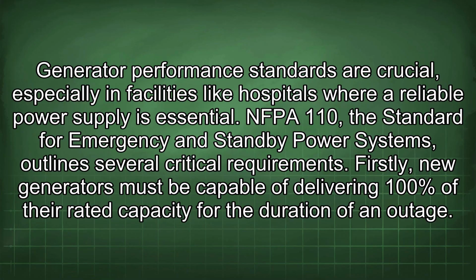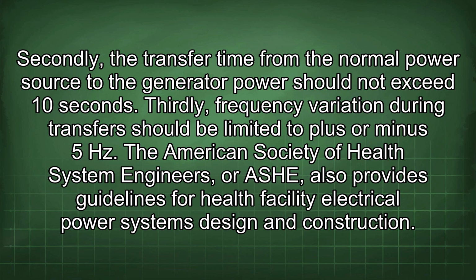Generator performance standards are crucial, especially in facilities like hospitals, where a reliable power supply is essential. NFPA 110, the standard for emergency and standby power systems, outlines several critical requirements. Firstly, new generators must be capable of delivering 100% of their rated capacity for the duration of an outage. Secondly, the transfer time from the normal power source to the generator power should not exceed 10 seconds. Thirdly, frequency variation during transfer should be limited to plus or minus 5 Hz.